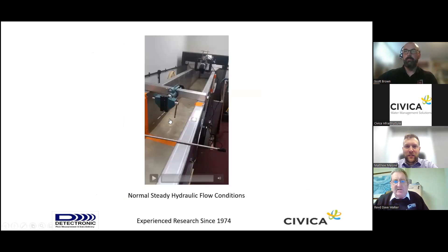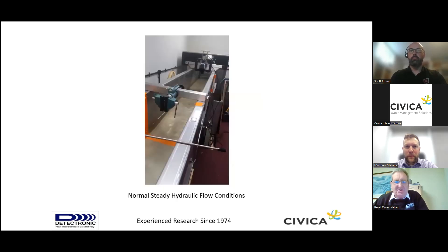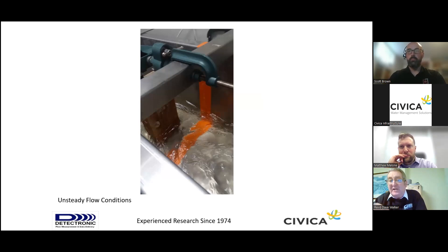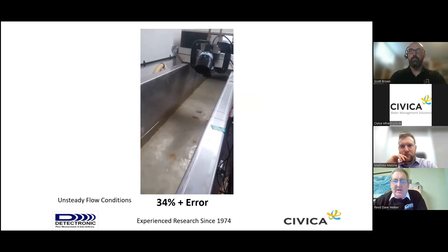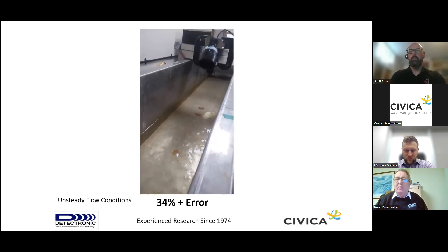On the next slide, I'm going to show some limitations using video of changing surface conditions for radar measurement. This is on a test rig at Detectronic. With normal, steady hydraulic flow, we were getting plus or minus 5% error from the radar device. When we put an obstruction just upstream to give a bit more turbulence on the surface ripple, you can see that a change in the velocity profile created an error of 34%. These are great technologies, but we need to know where the limitations lie, and as long as we work within those limitations, we can get some really good flow measurement.